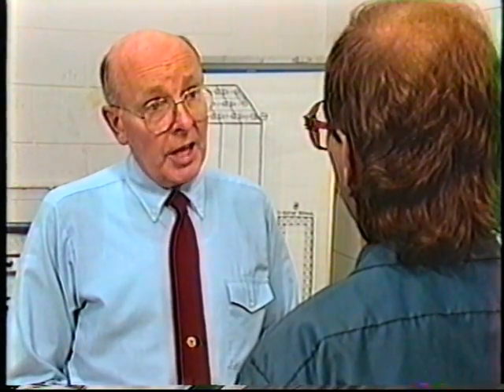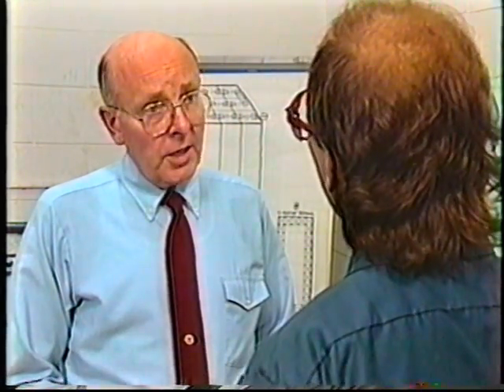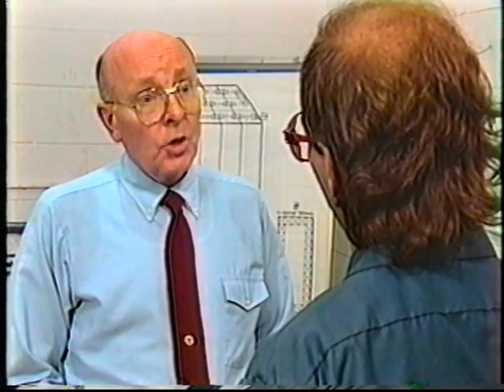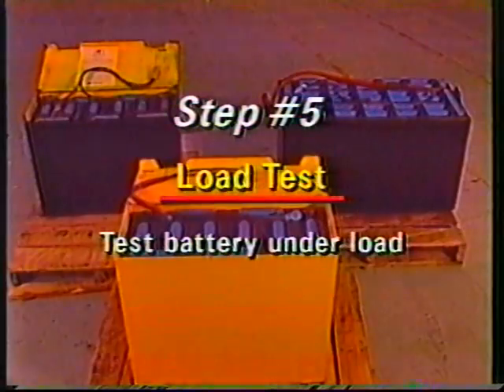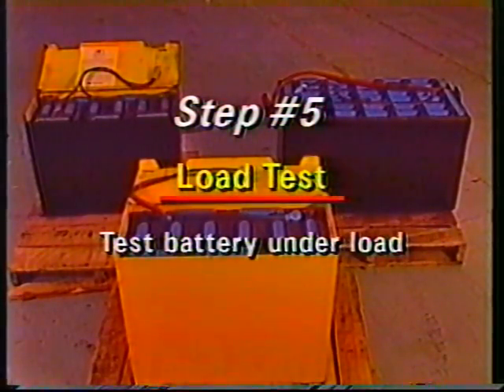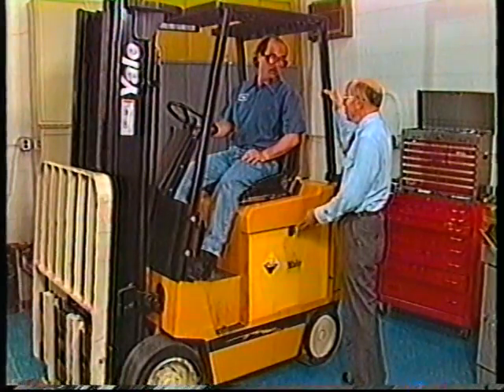In many cases, adjusting the specific gravity of a cell will restore most of the original amp-hour rating, depending on the battery's age. After correcting the specific gravity of a cell, you move on to the final test, the load test. This test shows us how well the positive and negative plates of each cell react under a loaded condition. For this test, the battery must be in the truck.